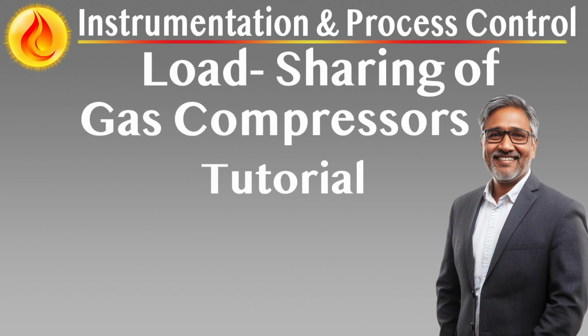Pressure override response. When pressure or flow deviates too rapidly or significantly from set point, a proportional integral PI loop counters the deviation. A predictive algorithm identifies excessive rate of change and adjusts recycle control proactively. Whichever signal, surge protection or pressure override, is greater is allowed to dominate. Guarantees pressure stability without compromising surge defense.